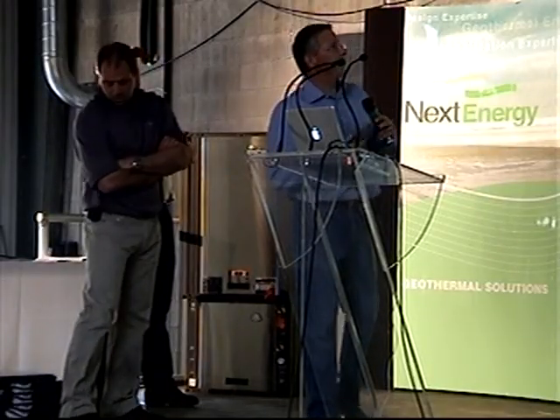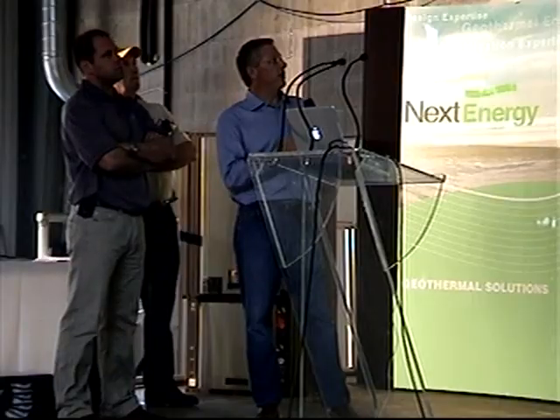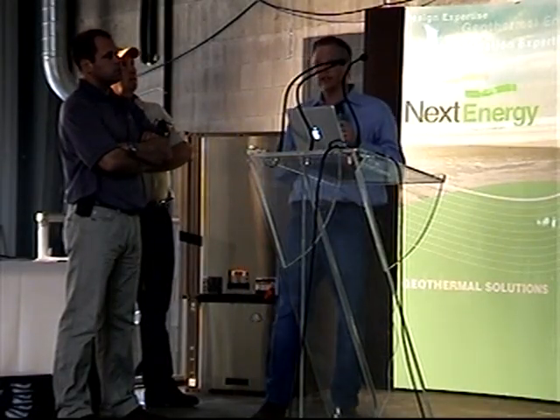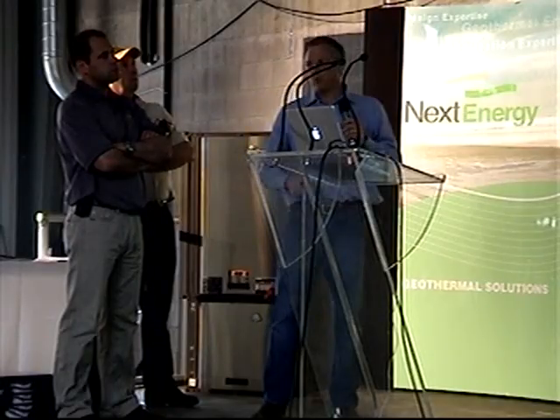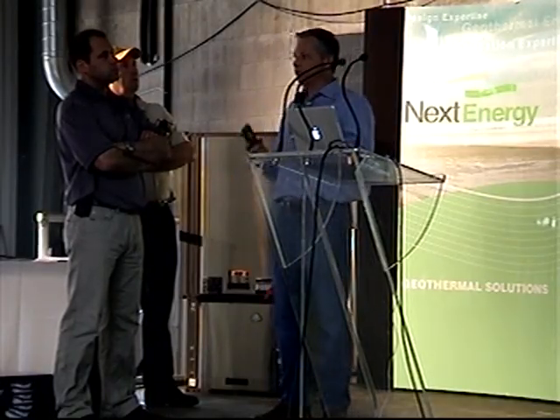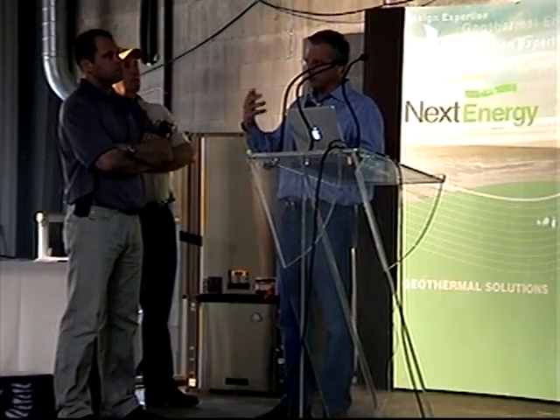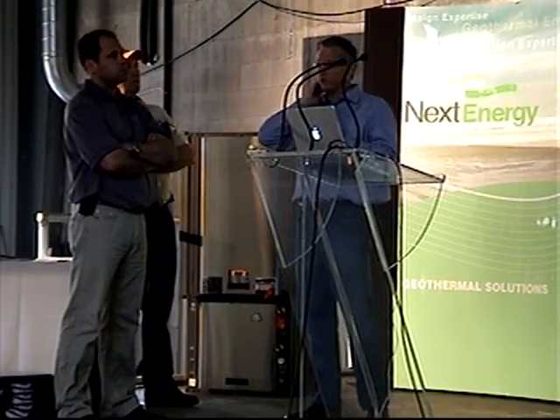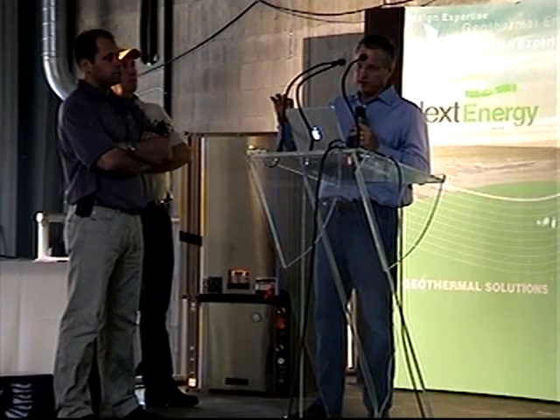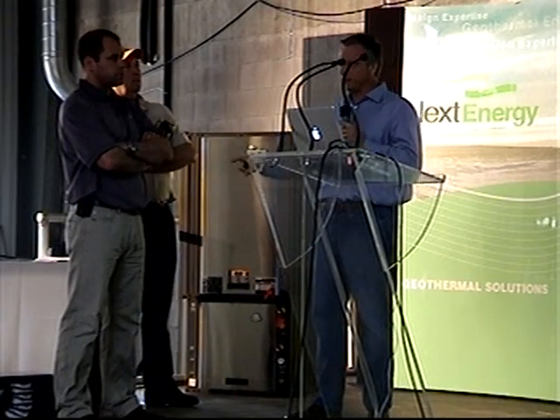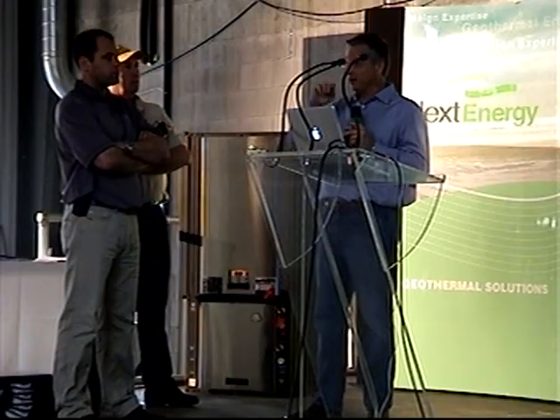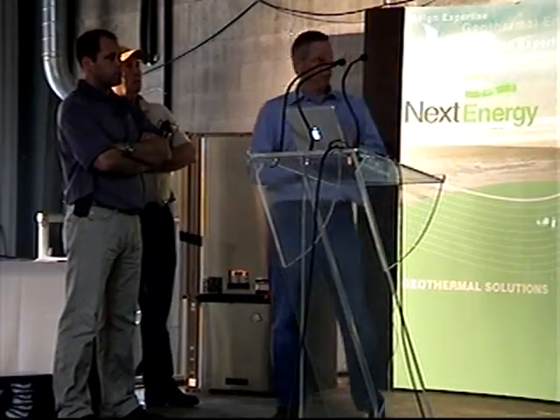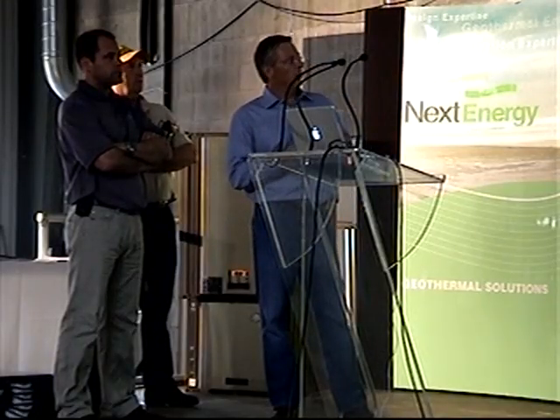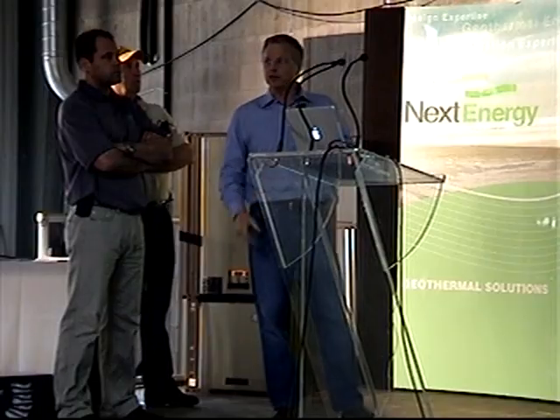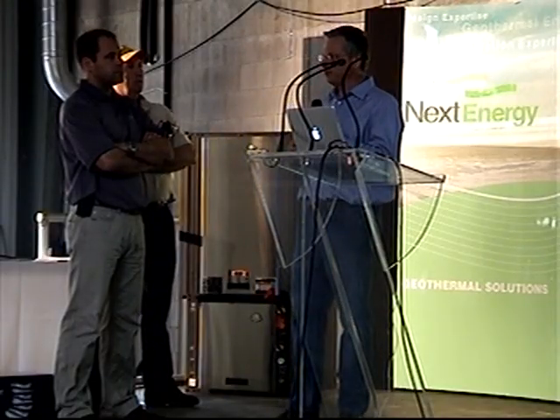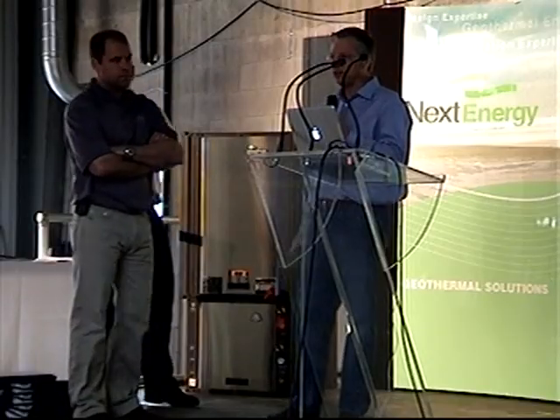Some of the features that we have on the safety side: we have a high pressure switch that ties in. We don't use a low pressure switch, we use a loss of charge switch, because what you're really trying to do is protect the compressor from running and overheating due to no refrigerant in the system. Low pressure switches are not very good freeze protection devices. Some people have done that, but you'll freeze up your coil by the time you trip a low pressure switch. One thing that has confused people is where our loss of charge switch is. I've had a lot of people say, you guys really screwed up, your low pressure switch is on the hot gas line.